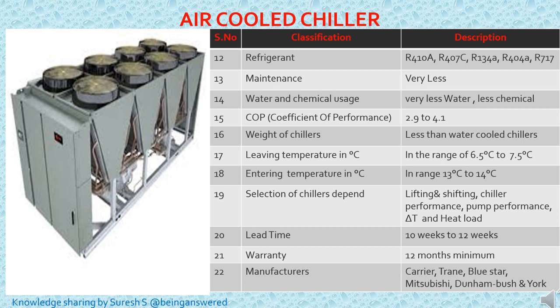The leaving temperature here will be 6.5 to 7.5 degrees centigrade. Again, the leaving temperature will be higher than the water cooled chiller. The lesser the leaving temperature, the better; we get more efficiency to achieve the temperature. Because the leaving temperature itself is 7.5, the return temperature will be 13 to 14 degrees. Selection of chillers again depends upon lifting, shifting, chiller performance and pump performance. Delta T is nothing but the difference in temperature. Again, the lead time is the same, 10 to 12 weeks, and the warranty is the same. Manufacturers, if you see, Carrier, Trane, Blue Star, Mitsubishi, all are players in the market.